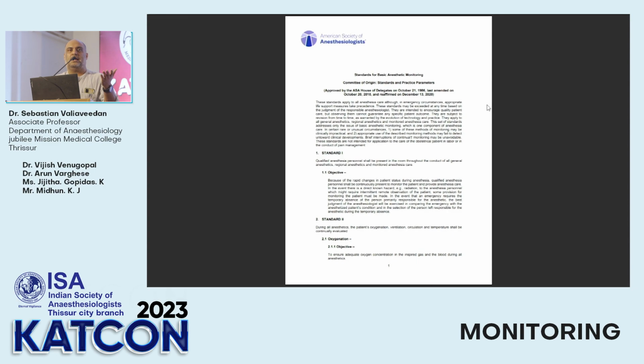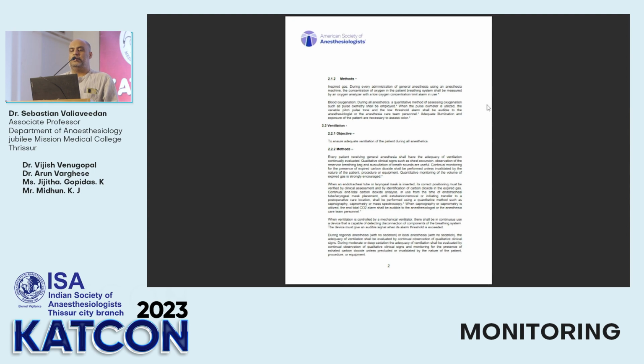And continuous would be like ECG, which is monitored continuously. Or arterial blood pressure is monitored continuously. So that is the distinction between continually and continuously. Now, for the monitoring of oxygenation, the objective is you monitor in 2 places: in the blood, the oxygen level, and also in the inspired oxygen, the circuit. Basically, the oxygen should not fall below a desired level in these 2 places. And for the inspired gas, during every administration of general anesthesia using an anesthesia machine, the concentration of oxygen in the patient system shall be measured using an oxygen analyzer with a low oxygen level alarm. That should also be functional and in place.